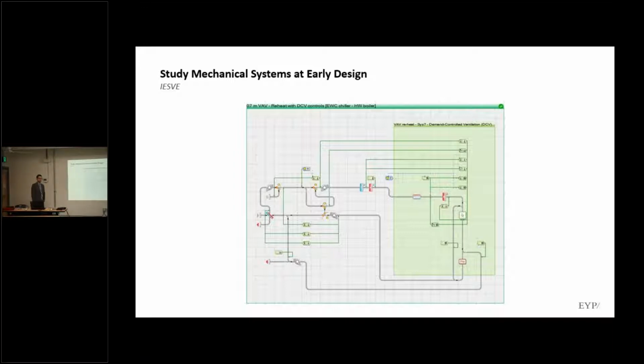We were really curious if an air-cooled chiller or a water-cooled chiller made the most sense. We had some limitations on the project, and the water-cooled chiller may not fit into the building, unfortunately. So we started saying, all right, what negative impact will we have if we went to the air-cooled chiller? We know water-cooled are more efficient. Can we make it up in other ways?